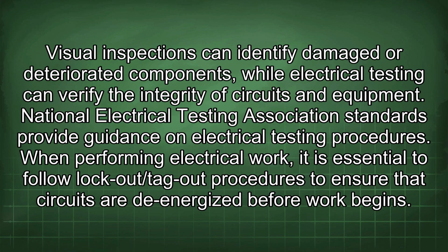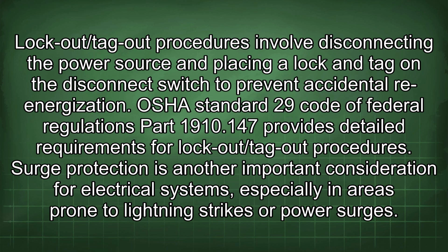National Electrical Testing Association standards provide guidance on electrical testing procedures. When performing electrical work, it is essential to follow lockout/tagout procedures to ensure that circuits are de-energized before work begins. Lockout/tagout procedures involve disconnecting the power source and placing a lock and tag on the disconnect switch to prevent accidental re-energization. OSHA Standard 29 Code of Federal Regulations Part 1910.147 provides detailed requirements for lockout/tagout procedures.